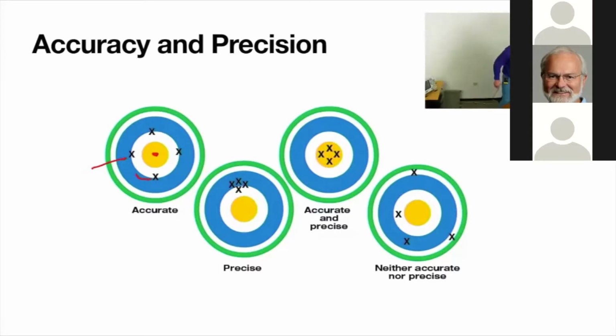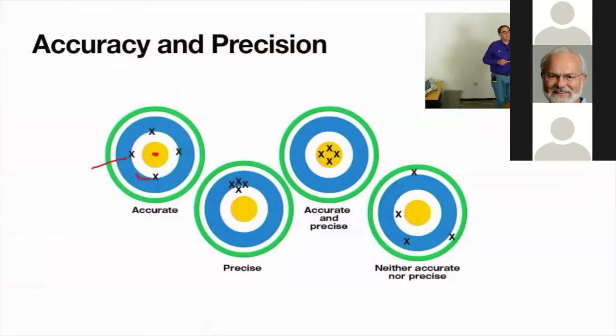Because of the laws of physics, we can't make a perfect measurement. There's always some uncertainty in the measurement, but we can do things when we design the test equipment to make it more accurate. We can correct for things like temperature variation, which affects the components, causes the measurements to vary and change. And for precision, we can add more bits, for example, to the analog to digital converter to get a little more precision. We combine those together, then we can design a piece of equipment that is both accurate and precise.